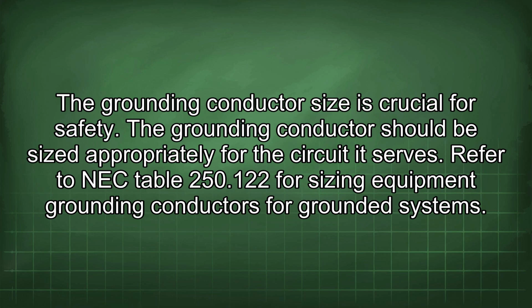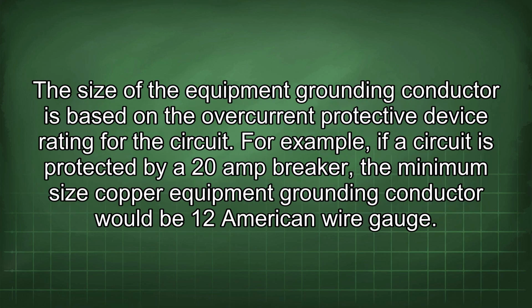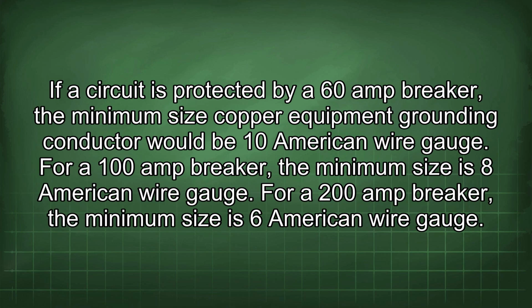Refer to NEC Table 250.122 for sizing equipment grounding conductors for grounded systems. The size of the equipment grounding conductor is based on the overcurrent protective device rating for the circuit. For example, if a circuit is protected by a 20 amp breaker, the minimum size copper equipment grounding conductor would be 12 American wire gauge. If a circuit is protected by a 60 amp breaker, the minimum size copper equipment grounding conductor would be 10 American wire gauge. For a 100 amp breaker, the minimum size is 8 American wire gauge.